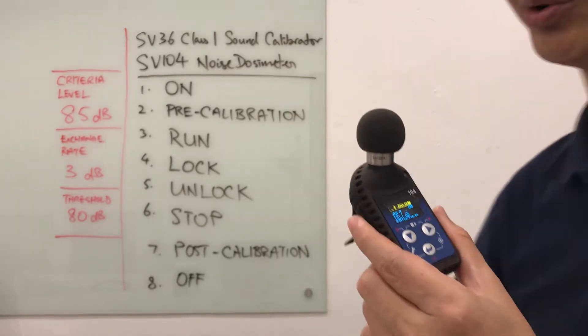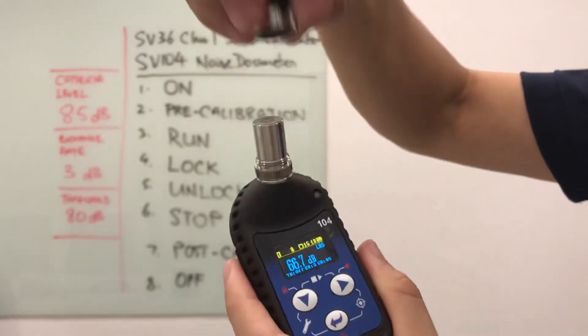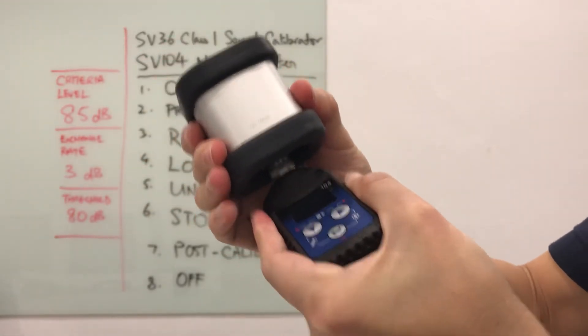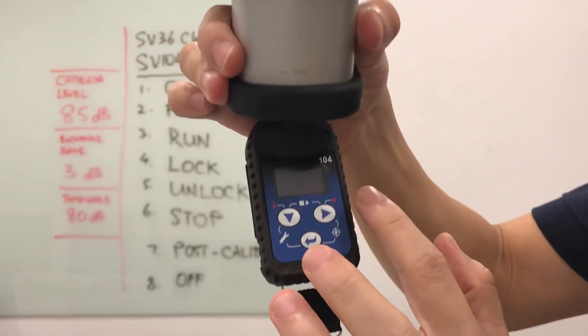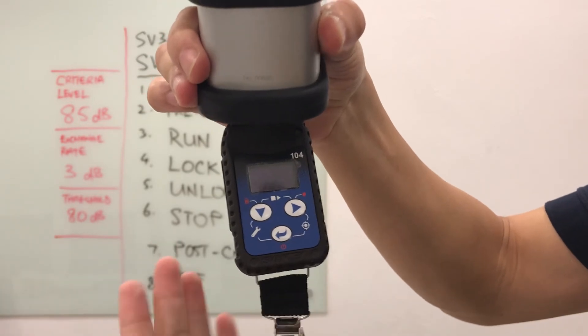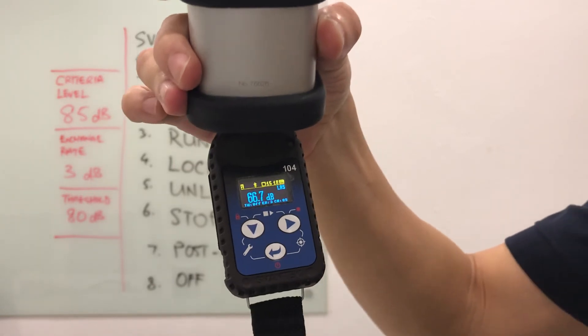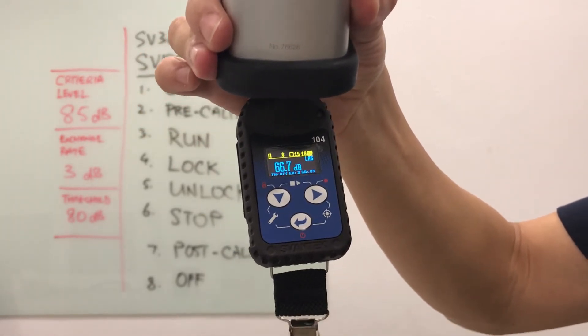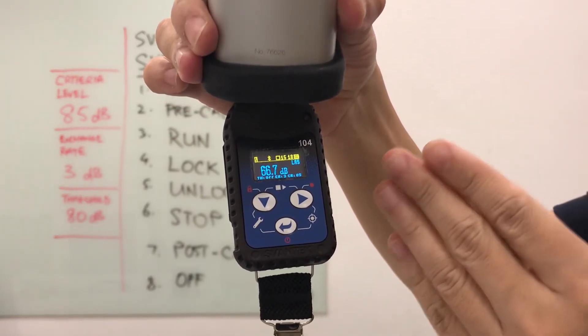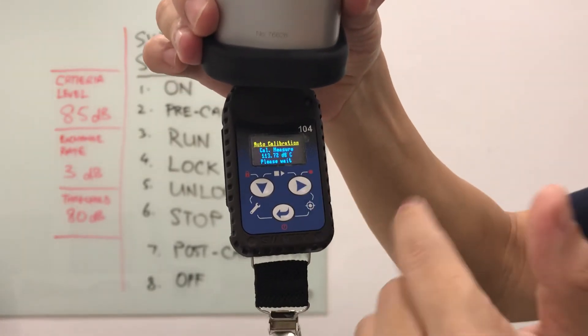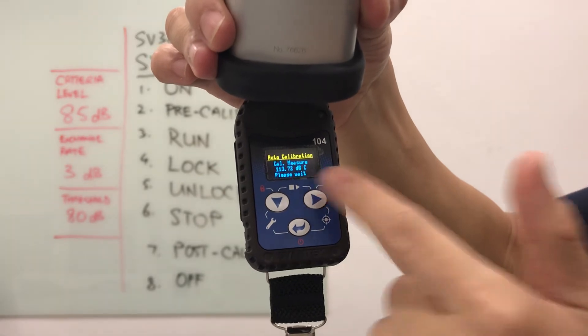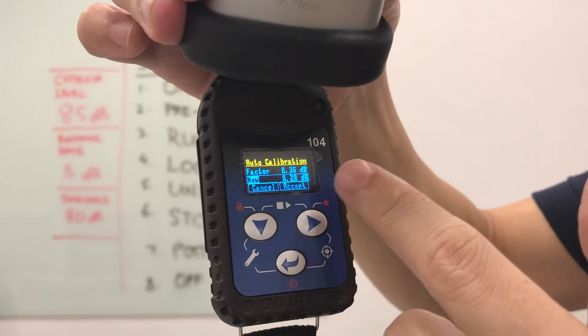The last step is to do a post-calibration. I'll unscrew the windscreen again and then insert the calibrator into the mic. Secure it. I'll make sure I select 114 because my instrument is set up with 114. The screen has gone into sleep again. Let me turn it back on. We can extend the sleep timer if you want to. At this stage, the dosimeter is sensing the calibrator at 114 dB and it goes into auto calibration.